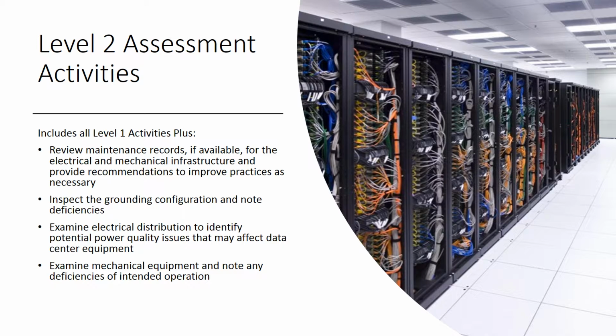During the Level 2 assessment, all of the activities completed during the Level 1 assessment will be completed along with a few more. This Level 2 assessment will include a review of all the maintenance records, if available, for the electrical and mechanical infrastructure, along with any recommendations to improve practices as necessary. An inspection of the grounding configuration will be completed and any deficiencies noted. The electrical distribution will be examined to identify potential power quality issues that may affect the data center equipment, and all of the mechanical equipment will be examined with any deficiencies of intended operation noted.